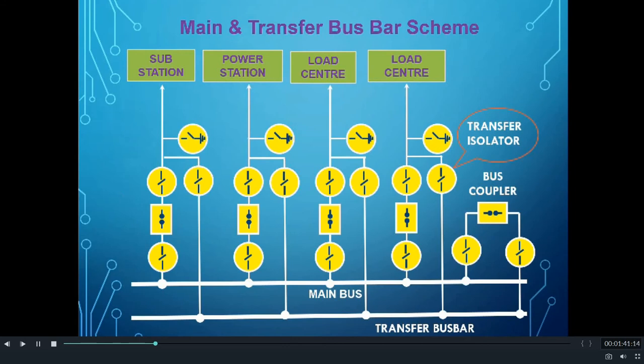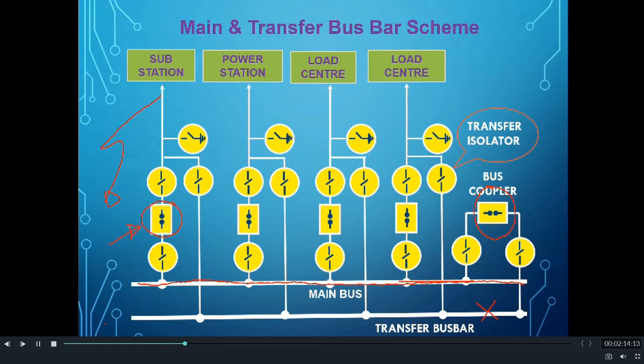Now we will see how LBB operates in a main and transfer busbar scheme. In main and transfer busbar scheme, all the feeders are connected to the main busbar and the transfer busbar is kept isolated — that is, the bus coupler connected between the main and transfer busbar is kept open always in normal condition. Hence, in this scheme also, due to the failure of a particular circuit breaker, all other circuit breakers connected to the main bus will be operated because of the generation of LBB. The LBB scheme for the single busbar scheme as well as the main and transfer busbar scheme will therefore be the same.